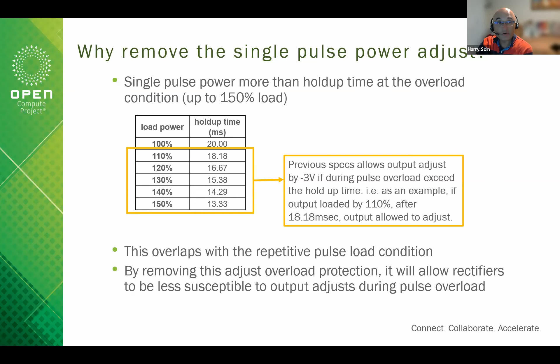As you can see here, a rectifier in the previous case would trigger as soon as we exceeded the hold-up time, for example at 18.18 milliseconds at 110% load, which is not a desired condition. So what has happened now, as we've moved on, here's an example of all the conditions and the benefits as we take that condition out and adjust for 150%.